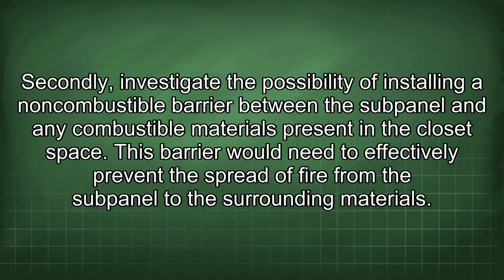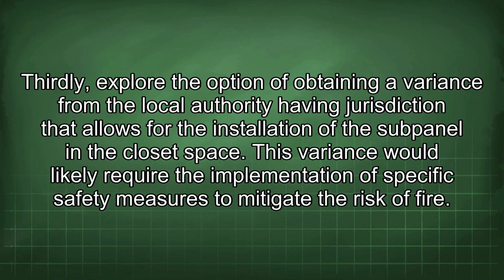Secondly, investigate the possibility of installing a non-combustible barrier between the subpanel and any combustible materials present in the closet space. This barrier would need to effectively prevent the spread of fire from the subpanel to the surrounding materials. Thirdly, explore the option of obtaining a variance from the local authority having jurisdiction that allows for the installation of the subpanel in the closet space. This variance would likely require the implementation of specific safety measures to mitigate the risk of fire.